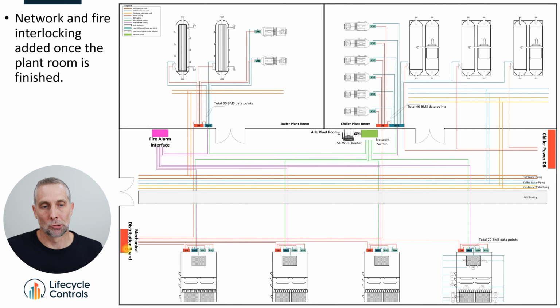Now this mechanical distribution board here, note I didn't call it a mechanical services switchboard or a mechanical control panel. I called it a mechanical distribution board. All that it is a standard off-the-shelf distribution board, just with circuit breakers. There's no hand-off-auto switches or undervolt fault lamps, and you're providing a mains feed to each one of the distributed mini distribution boards.